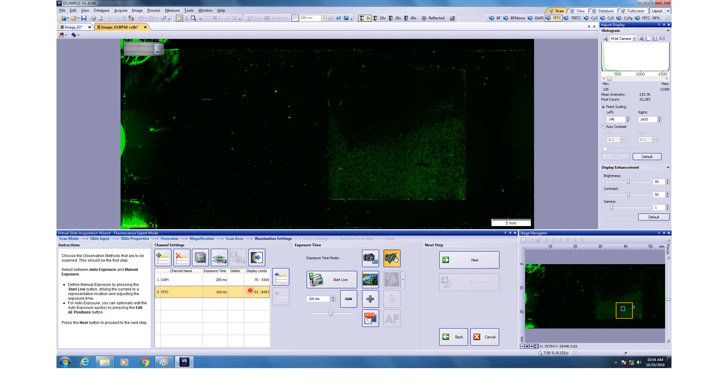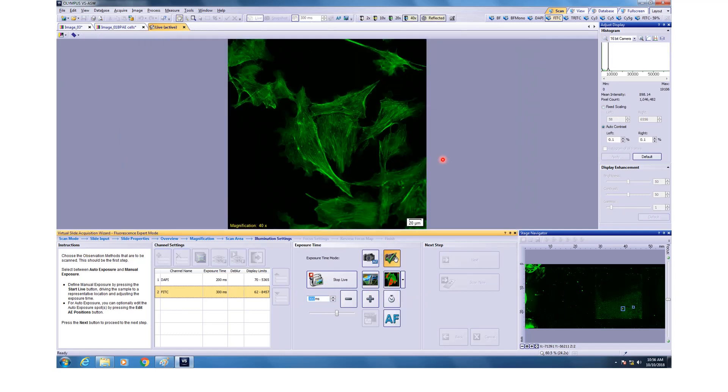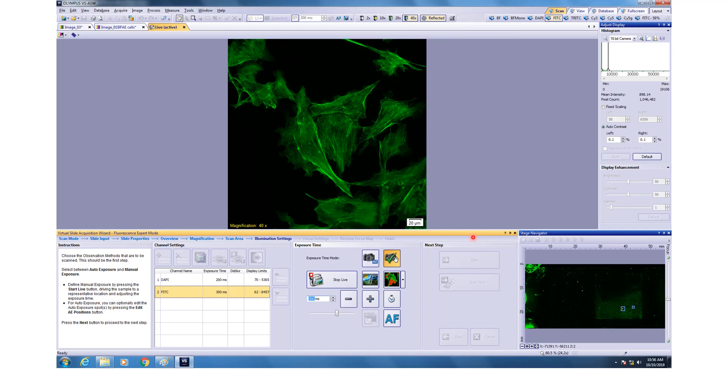After this, how do we select the exposure time? Again you can start live and see how the intensities are. For example, here if I click start live then I start seeing the cells in a better resolution. You can see that there is kind of good enough signal. But if you are not happy with this signal, you can notch up the exposure time. But for the sake of this example, I will be keeping at 300 milliseconds. And same way for DAPI I have also done. And you can actually navigate on the stage by clicking here anywhere very quickly. That way the navigation on stage is very fast. You don't need to always use the joystick.